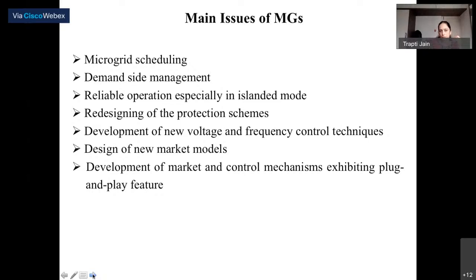Another issue is redesigning protection schemes. In conventional systems, when a fault occurs, the fault current becomes very high, almost 10 times the normal current, so it's easy to distinguish. But because microgrids use power electronic converters, the fault current is only about twice the normal current, making it very difficult for relays to distinguish between fault current and normal current. So we need to design new protection schemes that can make this distinction, and a lot of work is going on in this direction.